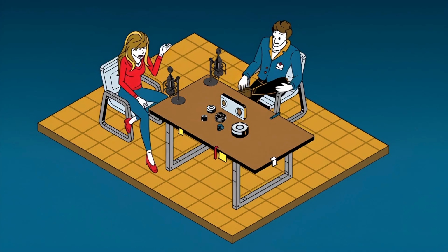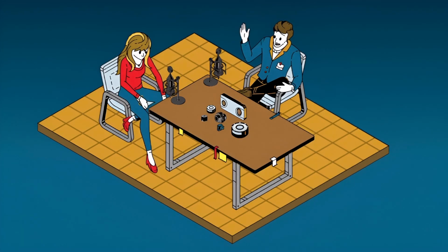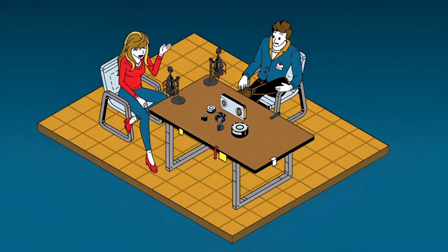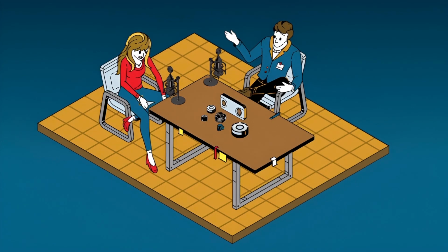You got it. You get distorted or corrupted readings that have nothing to do with the actual load you're applying. The main defense here is just robust, clean grounding through the whole system and using properly shielded cables. You have to protect that signal. It really sounds like even the best sensors are in a constant battle with physics and the environment. But knowing those risks, the million-dollar question becomes, how do we actually spot the damage early, before the data turns toxic? Right. Which brings us to section 2, 5 quick checks.